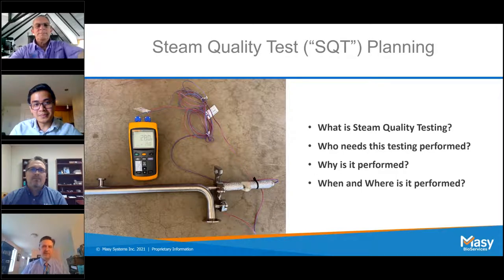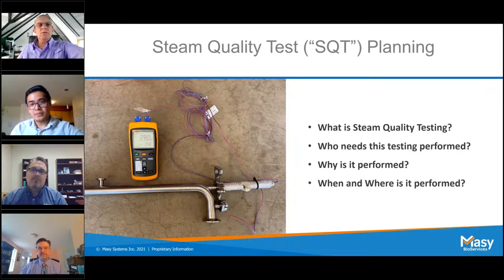Why is this performed? Sure. One of the reasons is that steam quality testing is performed to verify the steam supply assures product sterility. It's a requirement for manufacturers and processors of sterile products within the European community, and it's a logical practice in the steam sterilization sector.